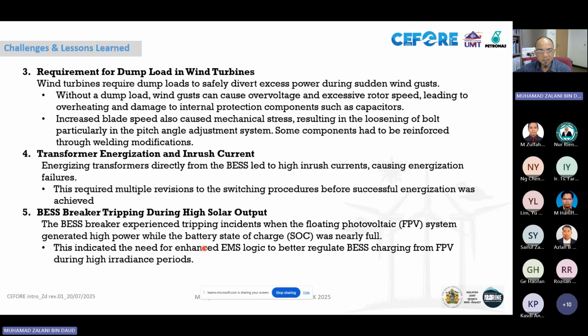So that's the case where we need a standard operation procedure for battery charging. In this commissioning stage, when state of charge reaches nearly 90-95%, our operator keeps an eye on the charging and controls the solar PV capacity to reduce it, so the BESS charges slowly. We're still fine-tuning the ETAP, IPAS, or SCADA system, so currently we're doing this manually in terms of control and optimization of our control philosophy.